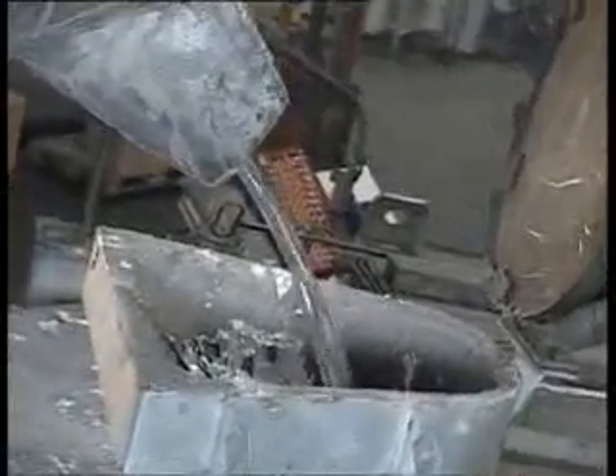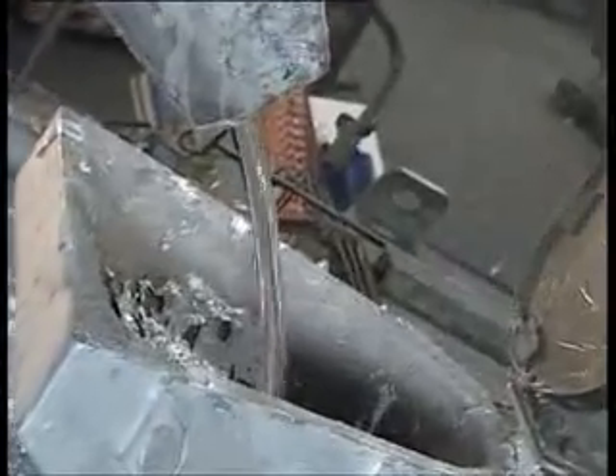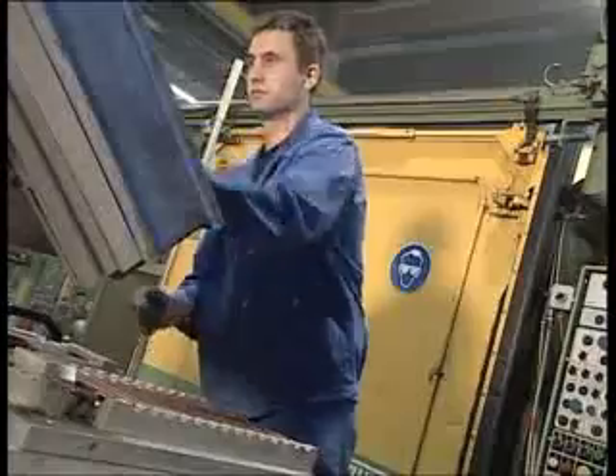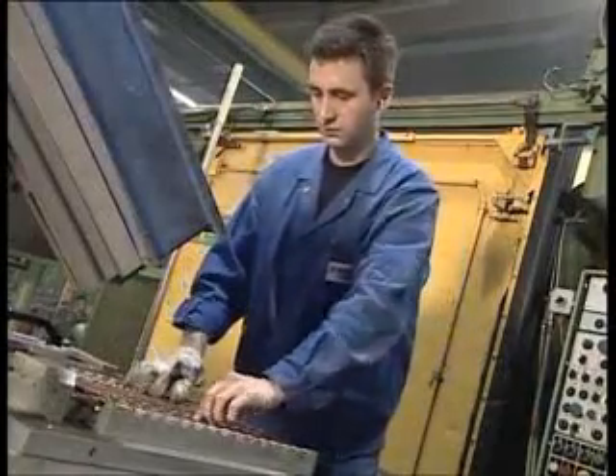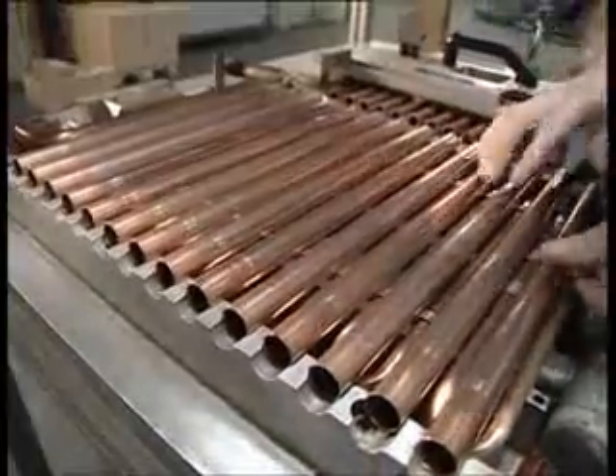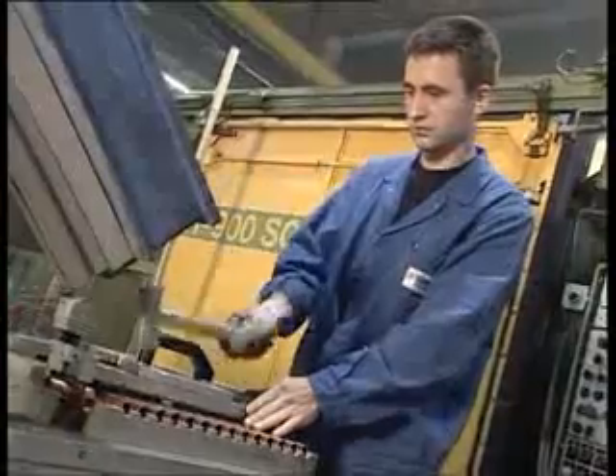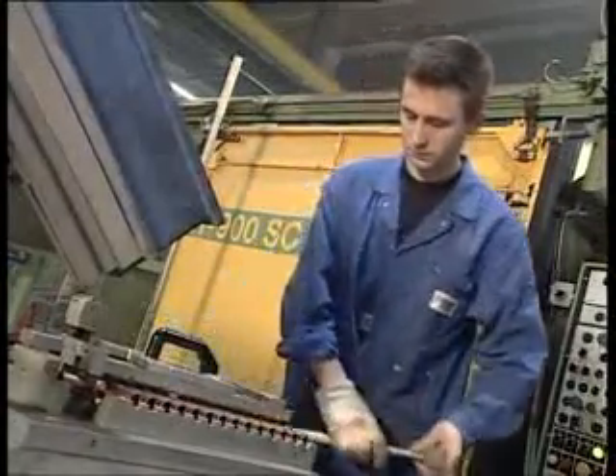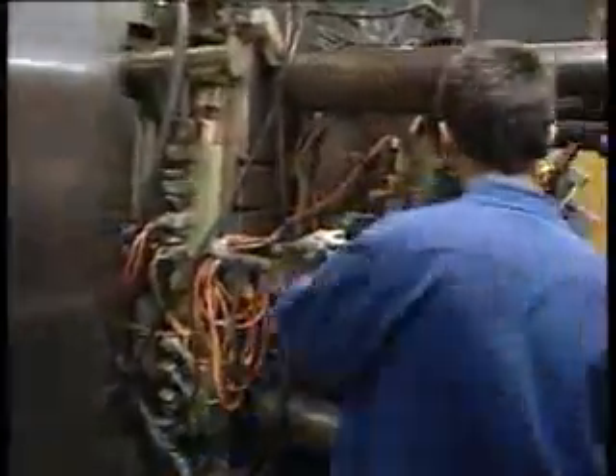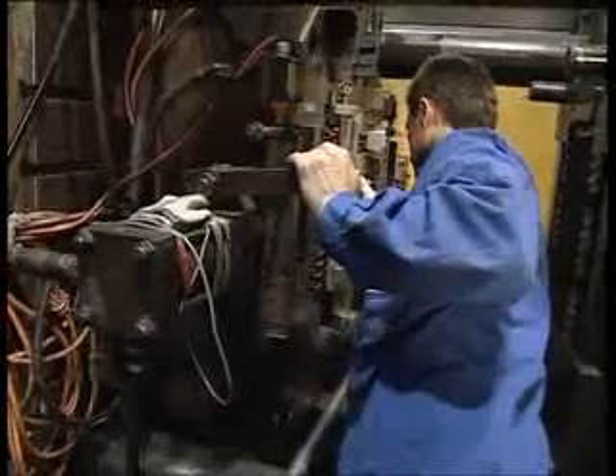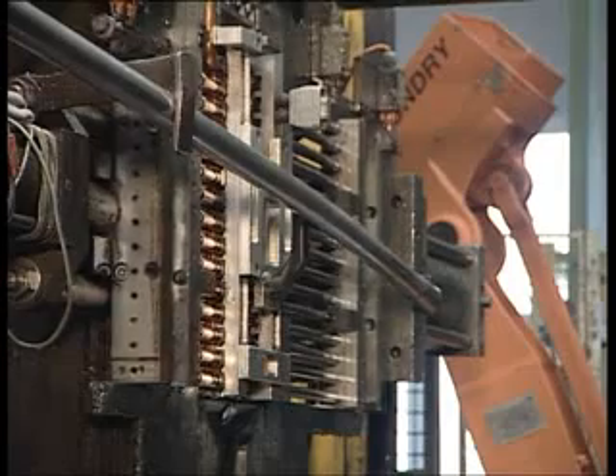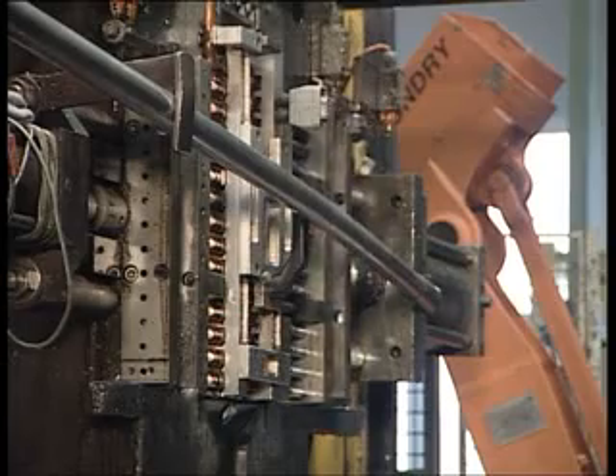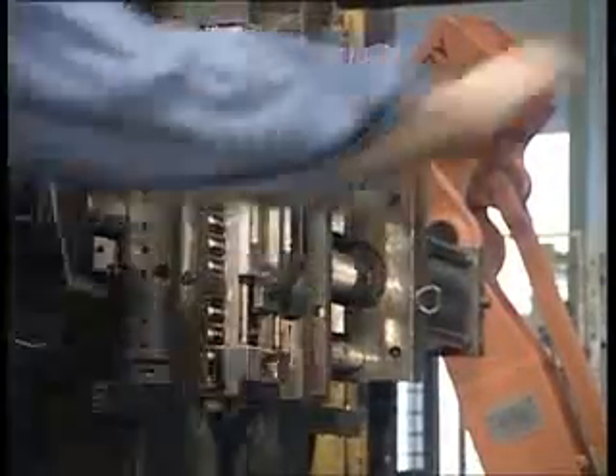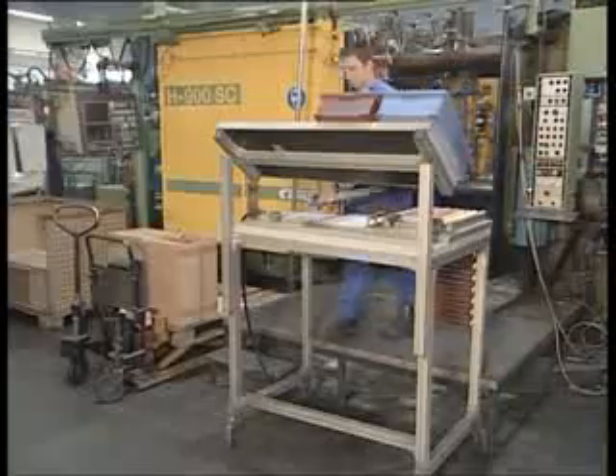In 1996, successful experiments were carried out in Germany with a 900-ton press with a shot control system, and the production of the heat exchanger for the Combi compact condensing boilers began. The first 1,000 boilers were successfully installed by a large housing corporation in Amsterdam. For the first time, open geysers were replaced by condensing combi boilers. A dream became reality. Now, 10 years later, a complete production cell has been set up for the production of heat exchangers, and more than 60,000 units are produced each year. A respectable number, with opportunities for growth, thanks to the foundry working 24 hours a day, 7 days a week.